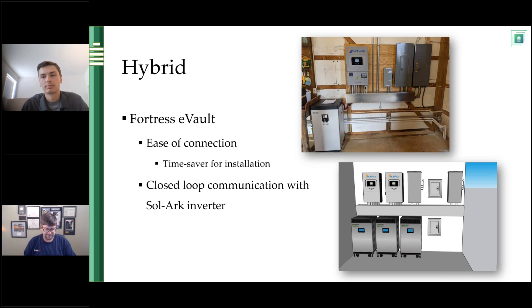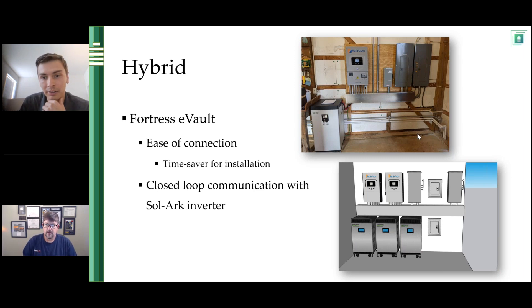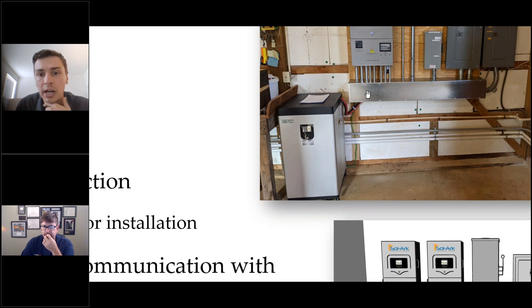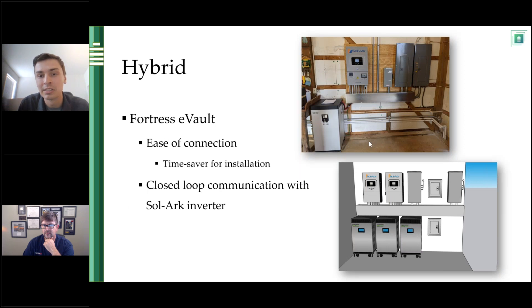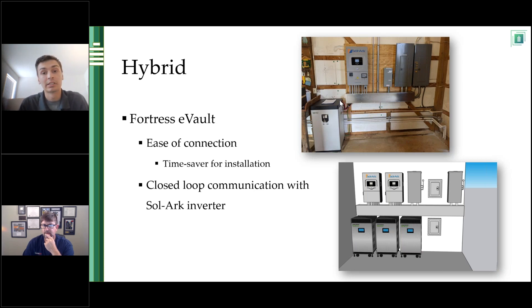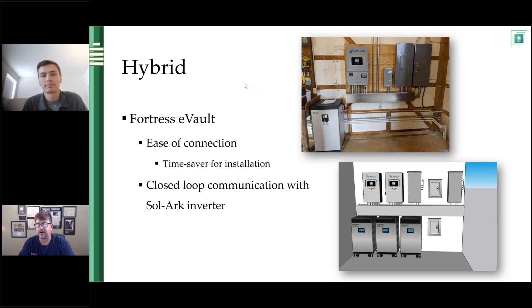Before jumping to Q&A, you mentioned ease of connection. With many lead acid batteries you'd be making connections from each battery across bus bars — lots of cables. But here, with Fortress, there is a positive and a negative four-gauge cable running into that combiner bus bar trough. Scott lands the connections there into his main panel, which runs into the SolarK converter. Instead of many batteries on the floor with cable after cable, it's just one battery. Six-foot run right into the combiner and you're good to go — it's landing right on the Sol-Ark breaker, that's it.